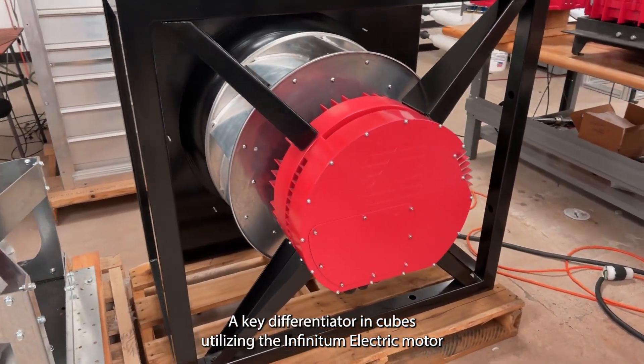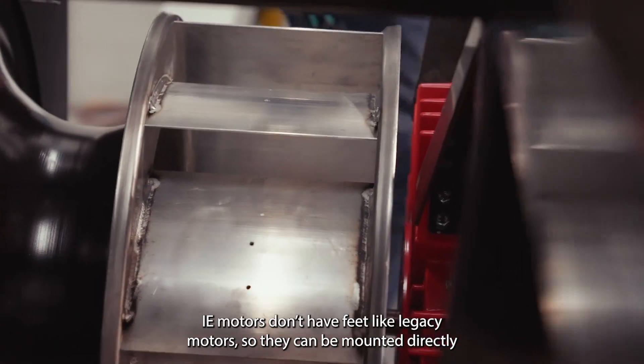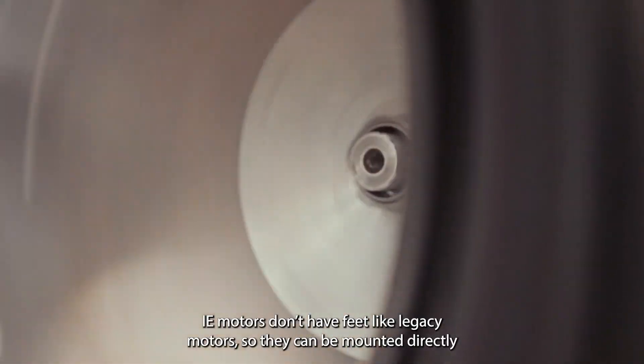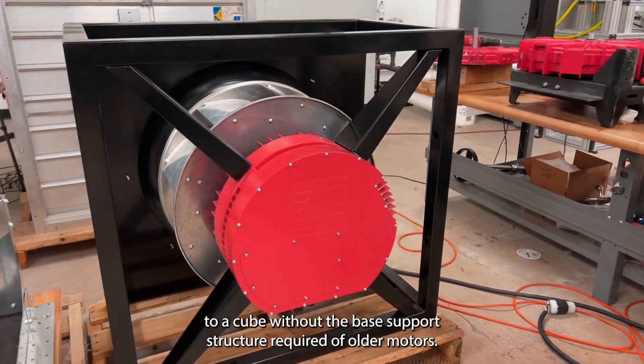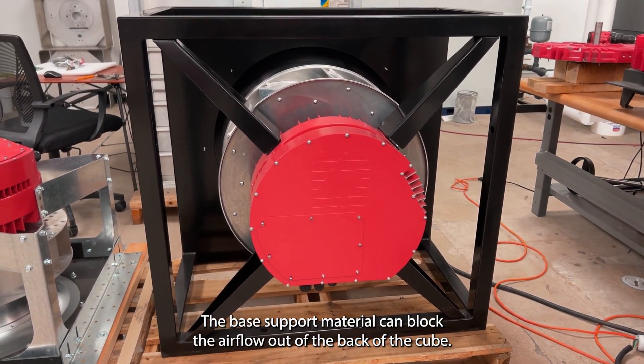A key differentiator on cubes utilizing the Infinitum electric motor is the star mounting design. IE motors don't have feet like legacy motors, so they can be mounted directly to a cube without the base support structure required of older motors. The base support material can block the air flow out of the back of the cube.